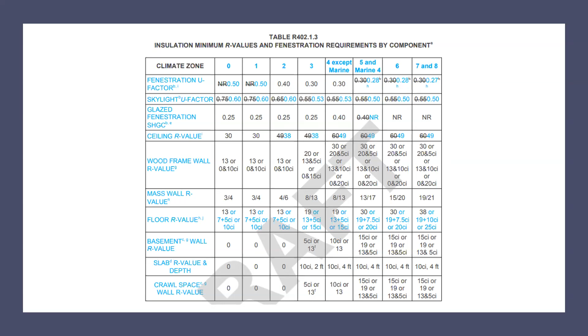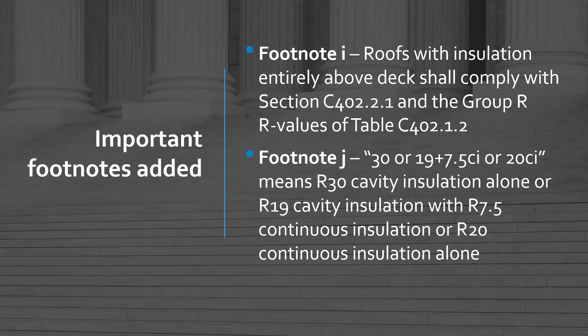Footnote I, roof insulation, same thing with the U. Then footnote J further defines what that means when adding it to the flooring insulation, where it says 30, or 19 plus 7.5, or 20, means 30 cavity insulation alone, or 19 with 7.5 continuous, or 20 continuous alone. We know that from previous code books, but they changed that and added another footnote to understand it a little differently.